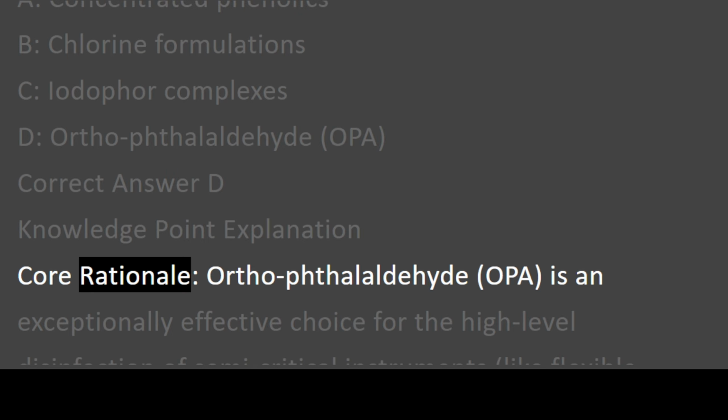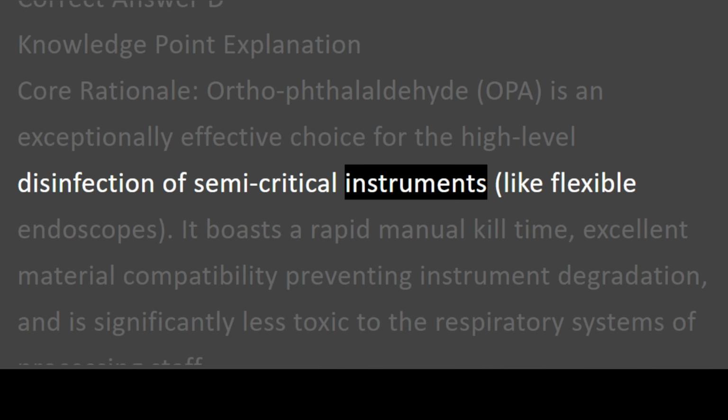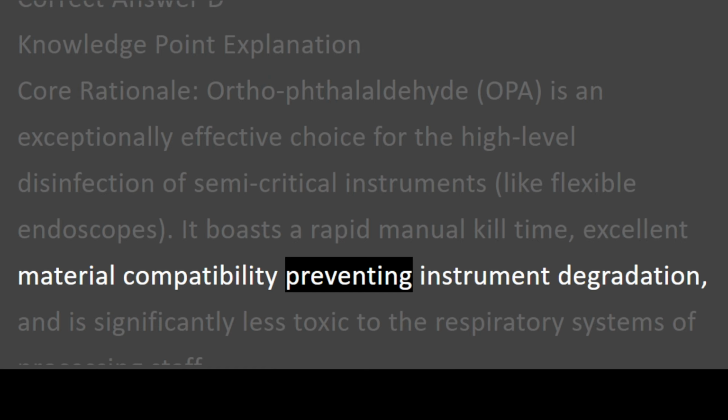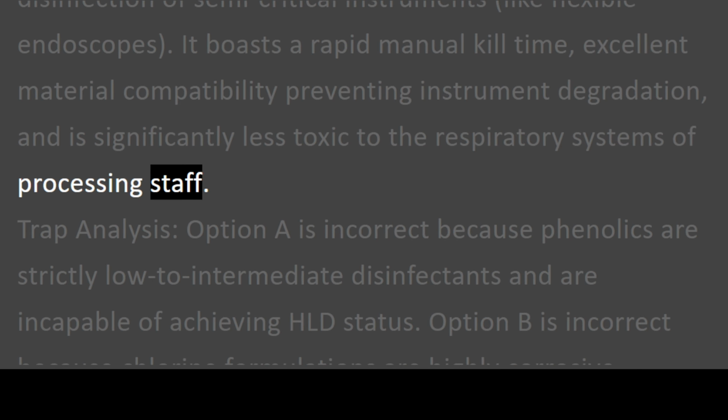Knowledge point explanation. Core rationale. Orthophthalaldehyde, OPA, is an exceptionally effective choice for the high-level disinfection of semi-critical instruments, like flexible endoscopes. It boasts a rapid manual kill time, excellent material compatibility preventing instrument degradation, and is significantly less toxic to the respiratory systems of processing staff.